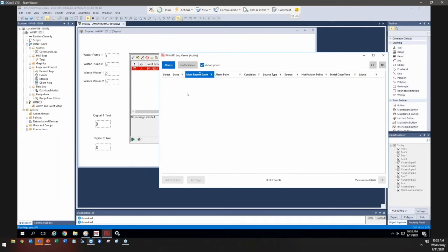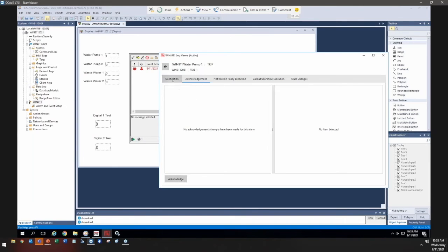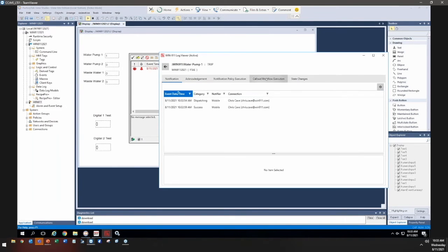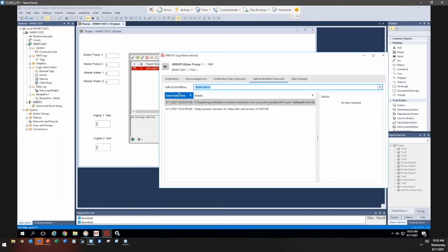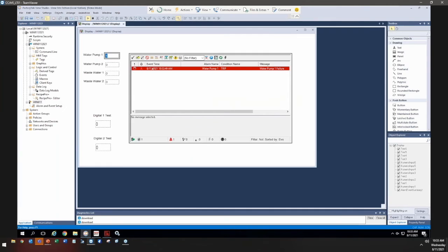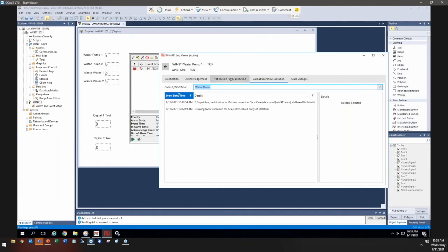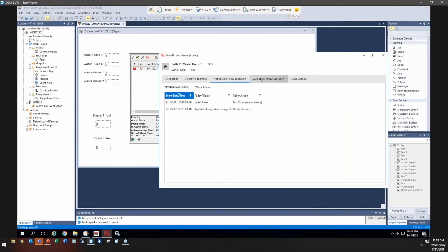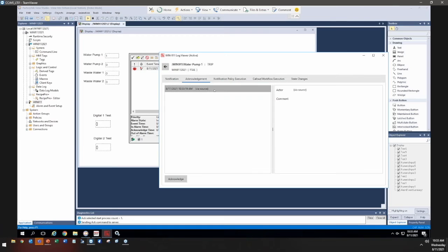Okay. So now we have a new initial event. Basically, the alarm lifecycle starts all over again. So new alarm, if we double click on it, new notifications, brand new call flow, where we've already sent out an email, sorry, a mobile connection, and then we're going to be waiting for our 1 minute. And so at this point, if we go with saying that the alarm is going to be acknowledged, I'm not going to see a follow-up email. If anything, we should see the fact that, yep, so we got one acknowledged here.